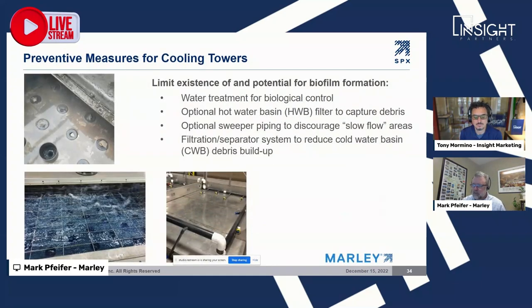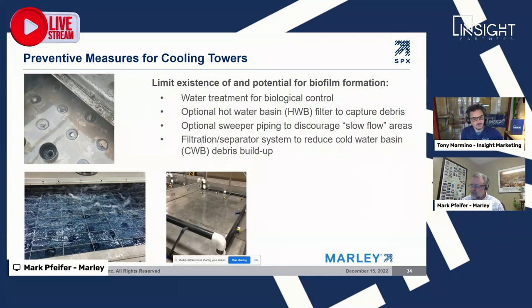We have options to help with water treatment that design engineers can specify. Pipe scale can come out of piping after operation — we have a filtration option that maintains good water distribution across all nozzles even as scale builds up on the filter. Sweeper piping is another option shown here that keeps suspended solids moving and not settling in the cooling tower basin, allowing them to be sent through a filtration or separator system.